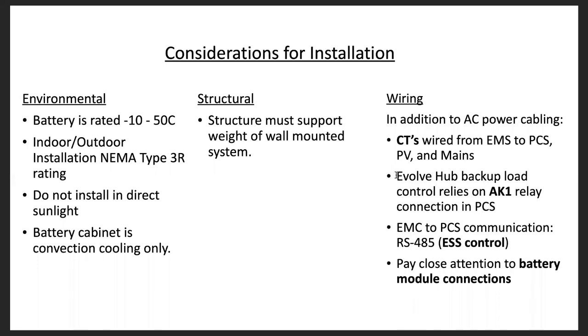As long as you adhere to the spacing guidelines shown in the manual as far as how close the EMS enclosure needs to be to the battery cabinet, all of the provided cables will work as is and won't need to be extended. The CTs are probably the primary thing that you, in most cases, will have to extend, or have the highest likelihood of needing to extend. So make sure that you use the right spec and type of crimps, no wire nuts on CTs and stuff like that. And of course, pay close attention to the battery module connection. The communications cabling especially is pretty specific. There's an input port and an output port for communications, and just a little bit of attention to detail will pay dividends in avoiding headaches.